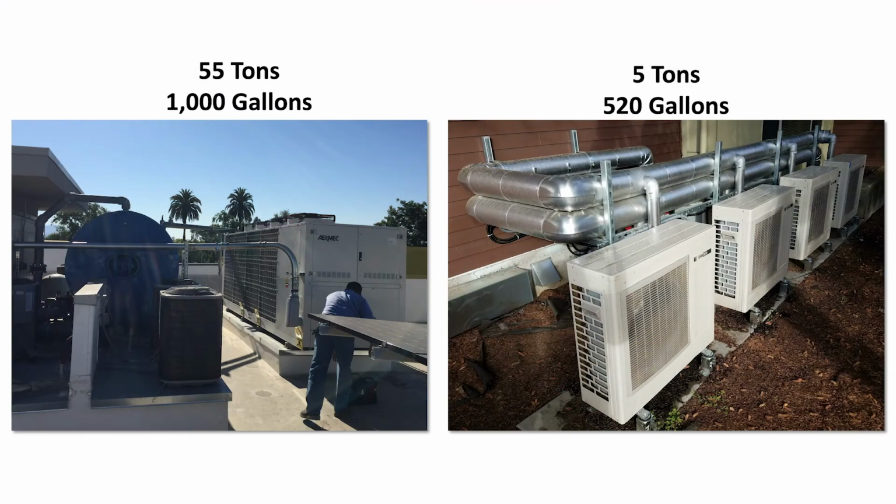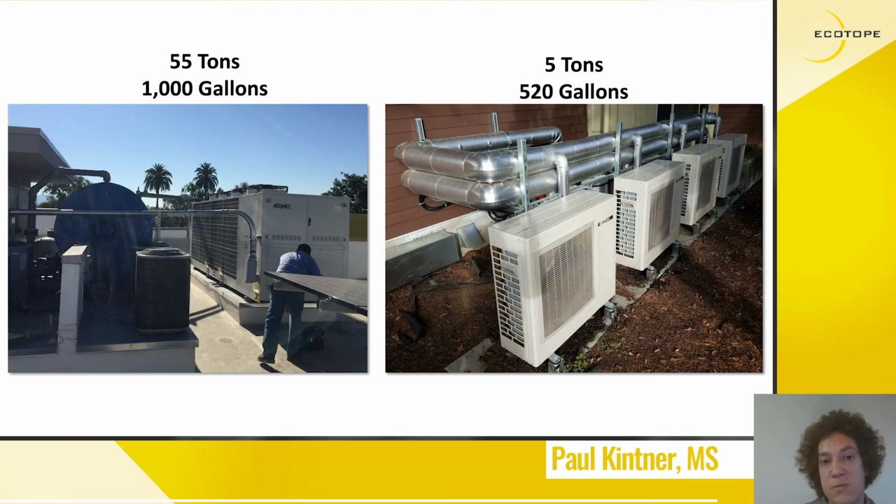The older sizing methodology, if people used it, would have been ASHRAE, which when people think about sizing these systems like boilers can lead to over double what is needed, creating a system that's very expensive and results in an unstable system and shortened lifespan of the equipment due to short cycling, which only adds into maintenance costs as well. These two systems shown here serve buildings with a similar number of units, but one operates with 1/10 of the heating capacity and a smart design, away from thinking about these systems as boilers.